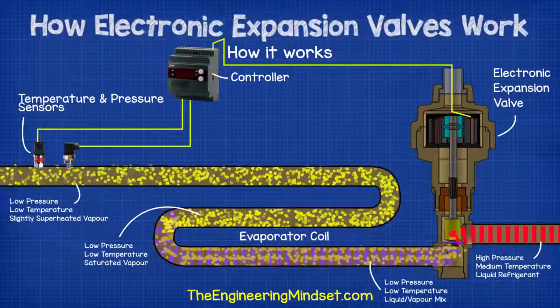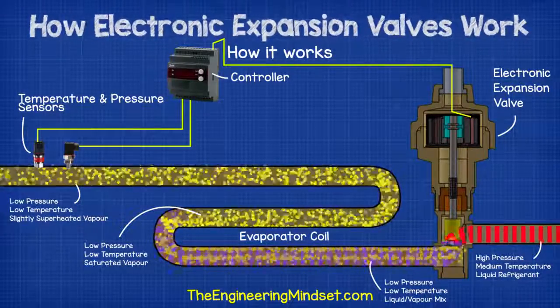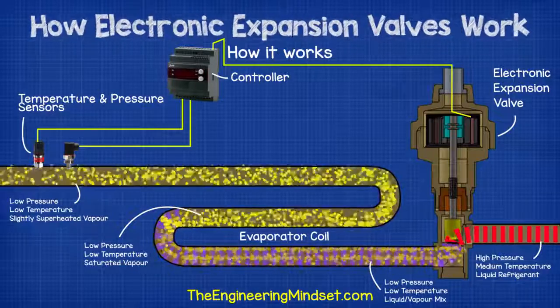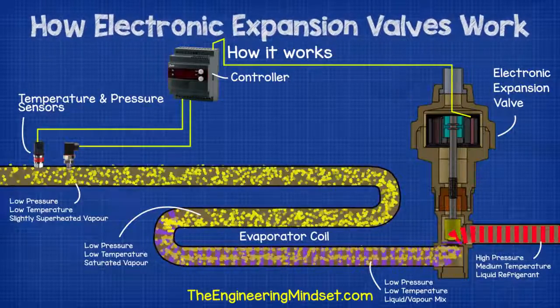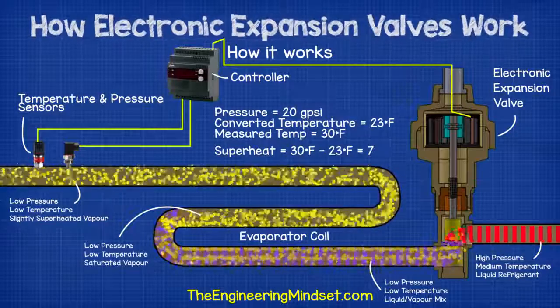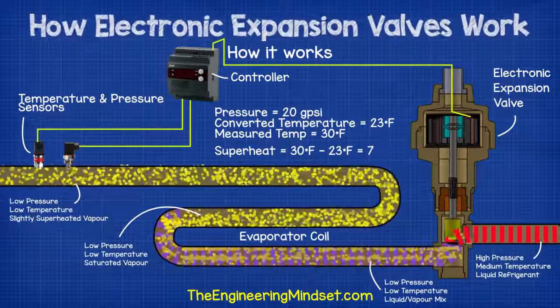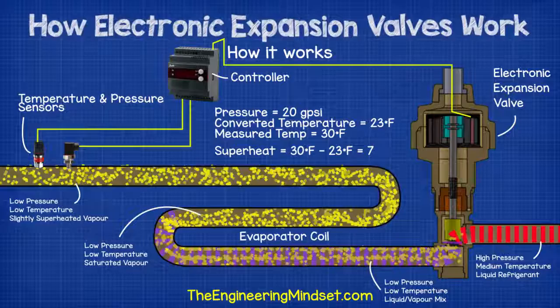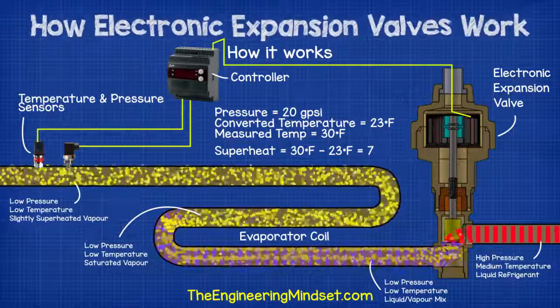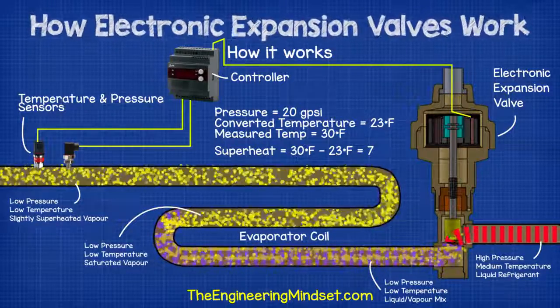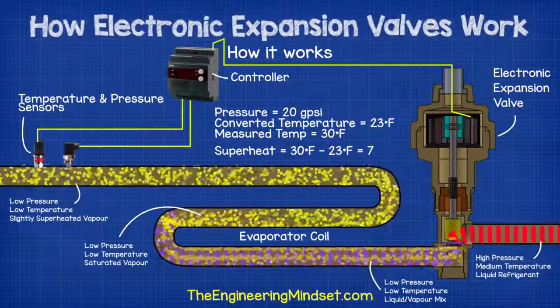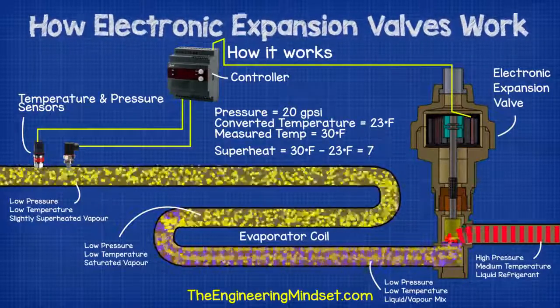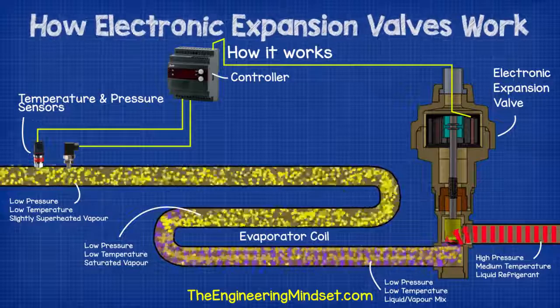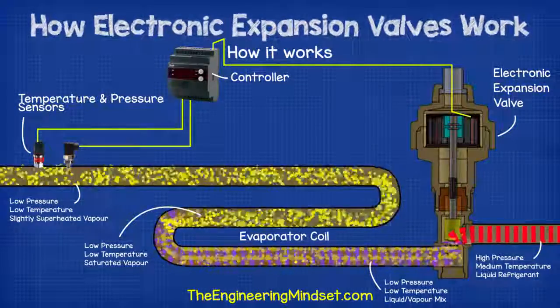The pressure is measured and converted by the controller, using stored data for the refrigerant being used in the system to find the saturation temperature. This is then compared to the actual temperature measurement. The difference between the two is the operating superheat. The controller then decides whether the expansion valve should open to let more refrigerant into the evaporator or close to reduce the amount entering.